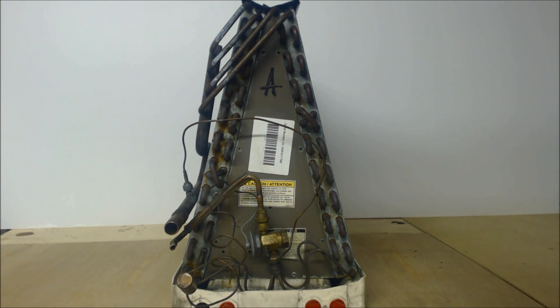You want to have it at its highest fan speed, which will be the black wire for a PSC motor. For variable speed, you've got to set the dip switches inside the unit to get maximum airflow across this coil.